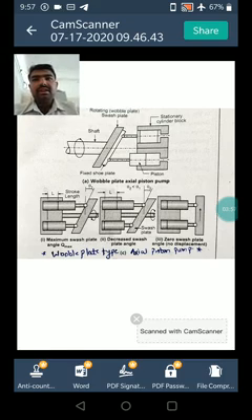Now, it is clear from the explanation in the preceding paragraphs that the stroke of the piston is determined by the angle of inclination of the swash plate with the vertical. When the swash plate is vertical, the stroke length of the piston is 0. Therefore, the volume flow rate from the pump can be varied by changing the swash plate angle.